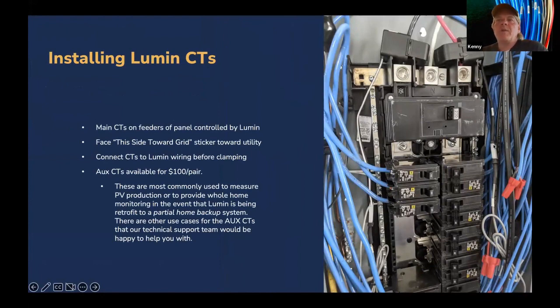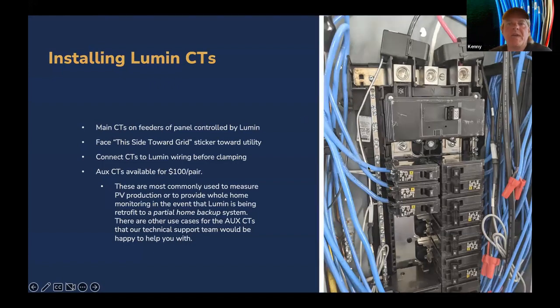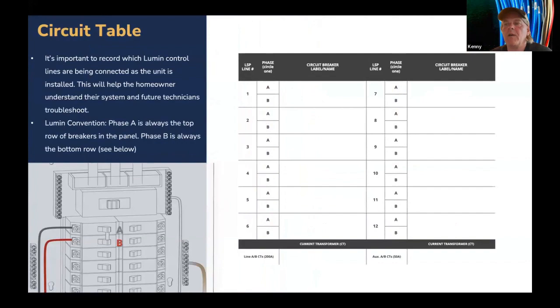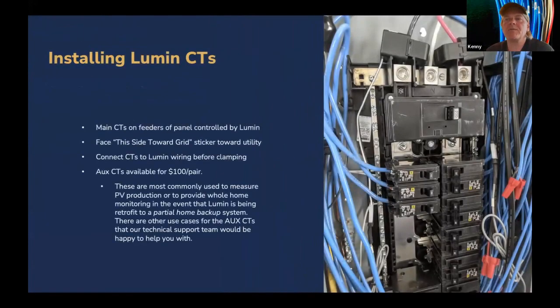Those are mounted on your feeder breakers, the feeders of the main backed up panel, unless you're going to use an auxiliary CT, which can be wrapped around your solar and PV system. That location would need to be moved out of the main feeders to above the MID or transfer switch. Face this side toward the grid sticker, and that will do your everything else calculation, so you can monitor everything on that panel.